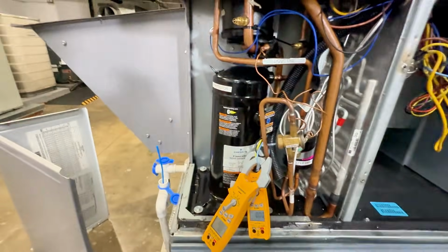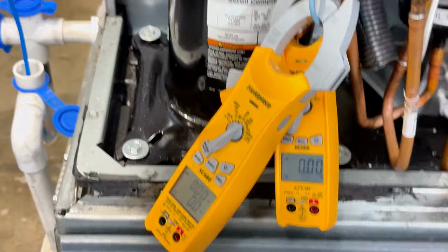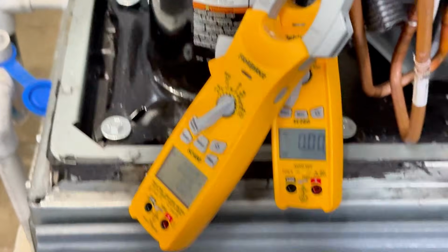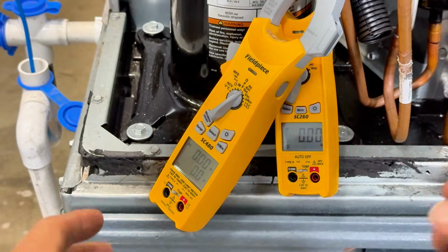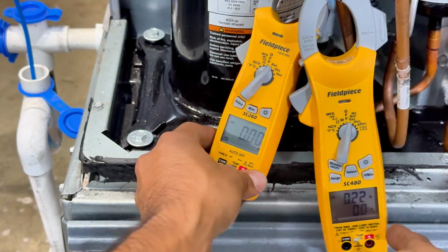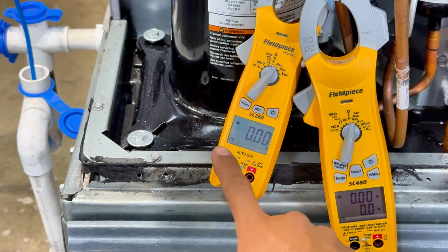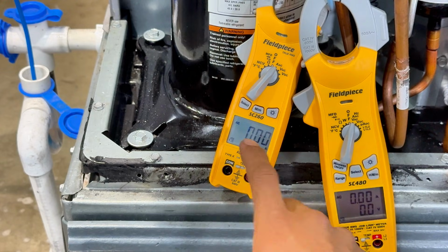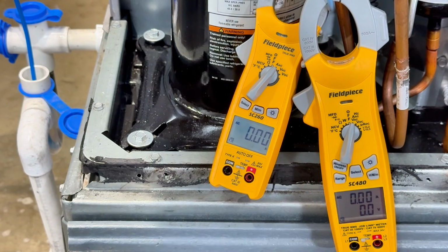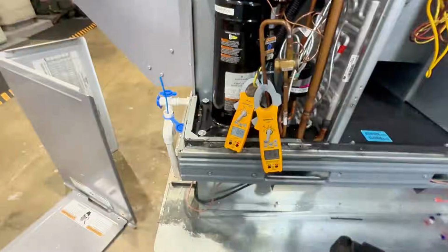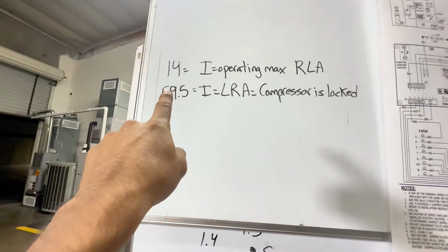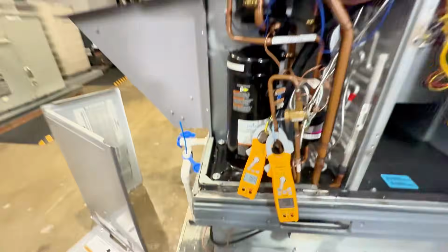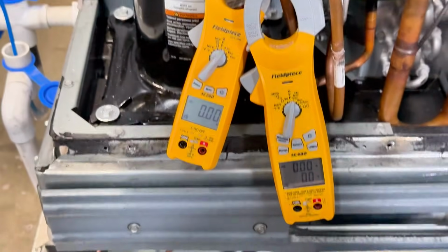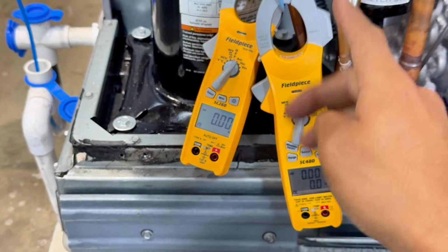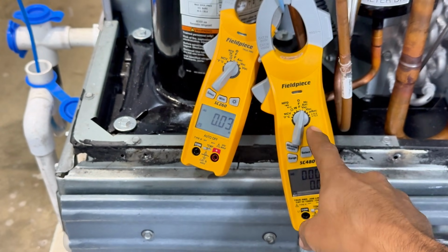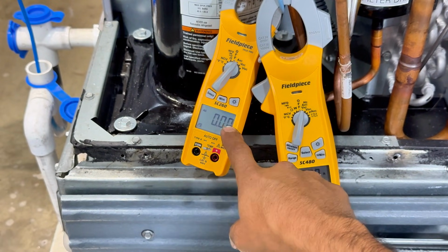Now that I removed it, I want you to see what's going on with those numbers. It's going to happen pretty fast, so you have to keep an eye on it. Start winding, run winding. Look at what happens to this one here. You remember that number? 59.5 when the compressor locks. So keep an eye on that number. This is the start winding and my run winding, and look at this number here.